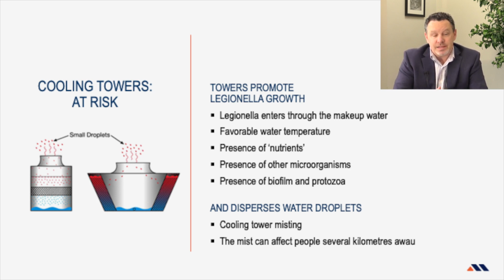Today, like I said, we're talking about cooling towers specifically, because there are some other systems where it could be found. How does the bacteria get in? It comes in through the makeup water. A lot of people are sometimes surprised to know that, because we think our cooling tower is using city potable water, which is perfectly clean. The reality is it's not perfectly clean, and sometimes Legionella can come through. By far the most common source of Legionella contamination is the makeup water.